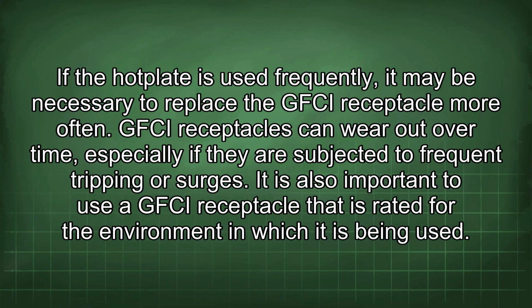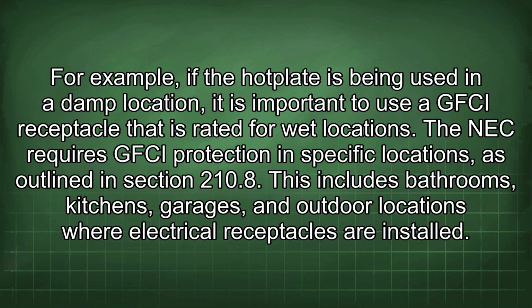If the hot plate is used frequently, it may be necessary to replace the GFCI receptacle more often. GFCI receptacles can wear out over time, especially if they are subjected to frequent tripping or surges. It is also important to use a GFCI receptacle that is rated for the environment in which it is being used. For example, if the hot plate is being used in a damp location, it is important to use a GFCI receptacle that is rated for wet locations.